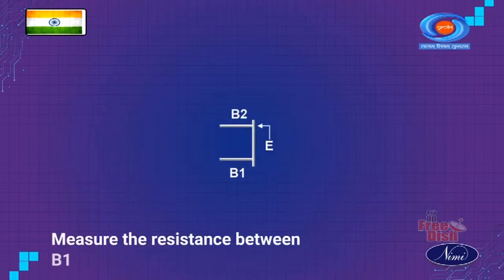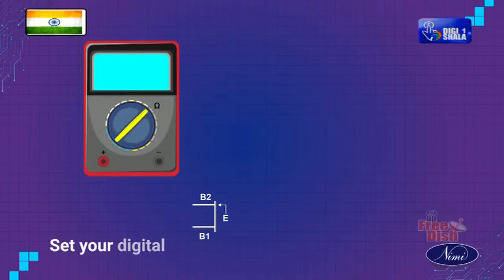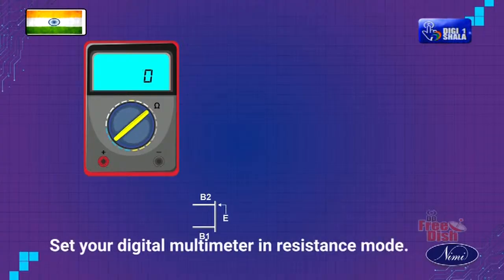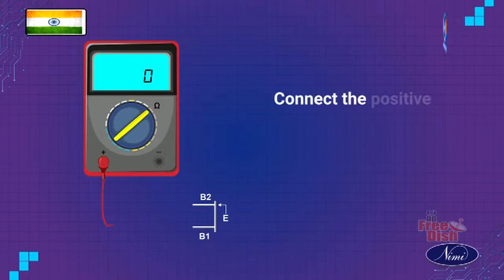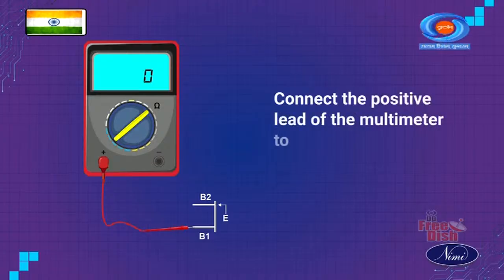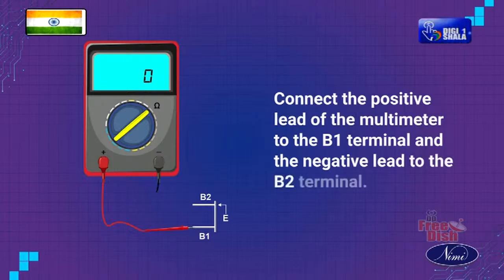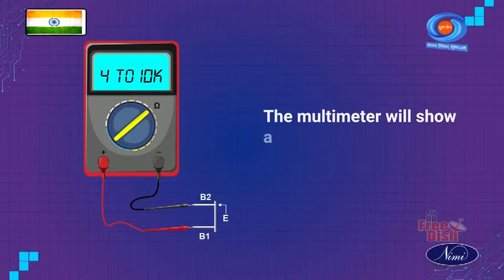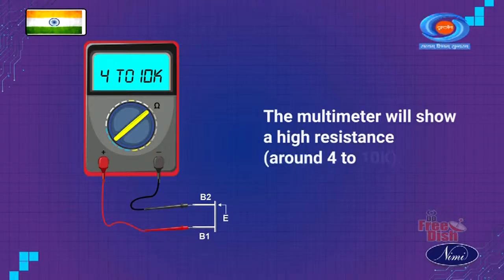Measure the resistance between B1 and B2 terminals. Set your digital multimeter in resistance mode. Connect the positive lead to the B1 terminal and the negative lead to the B2 terminal. The multimeter will show a high resistance around 4 to 10K.